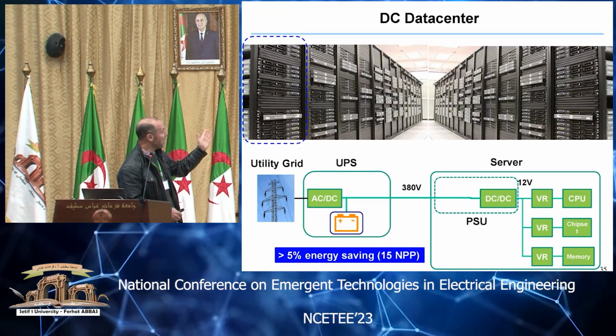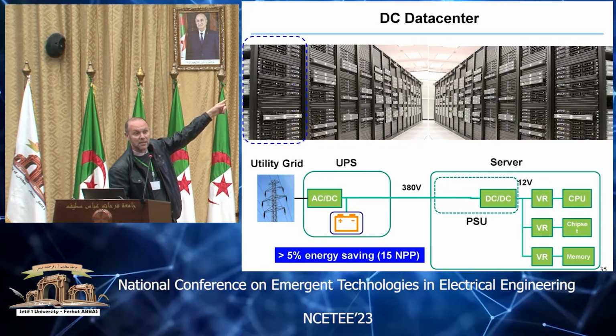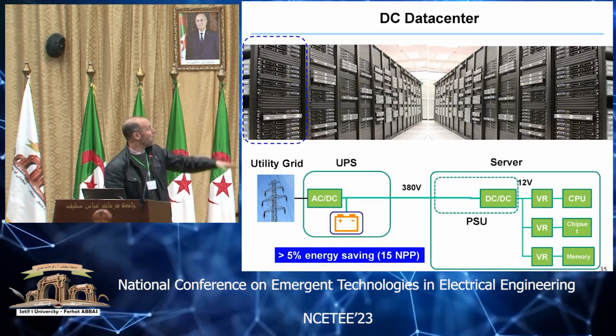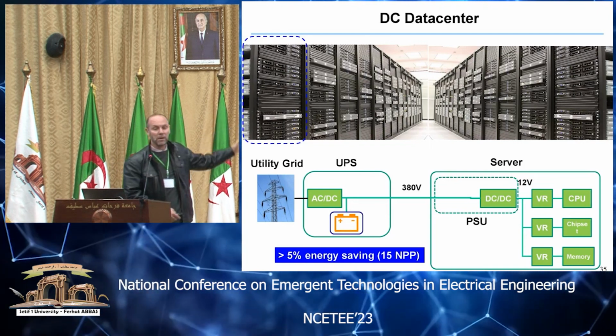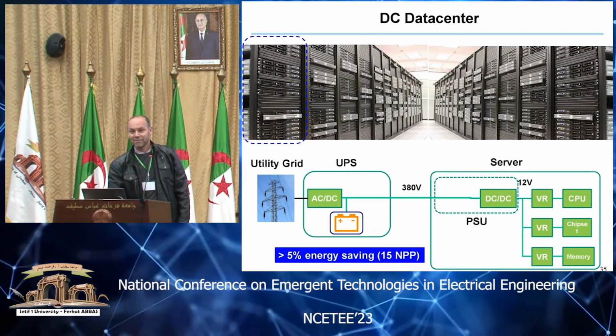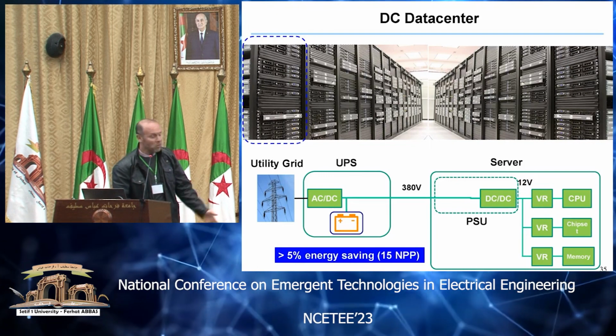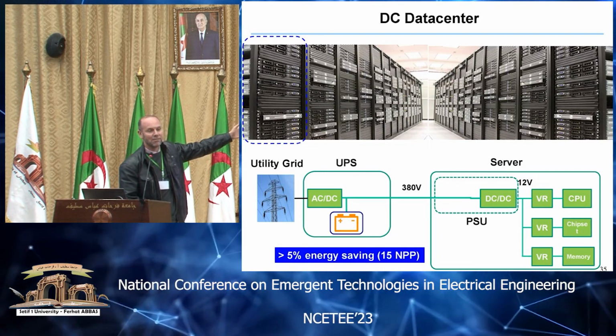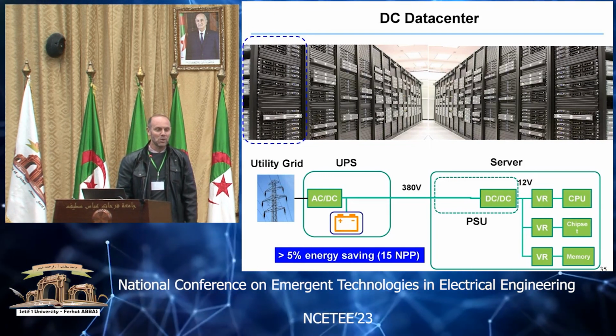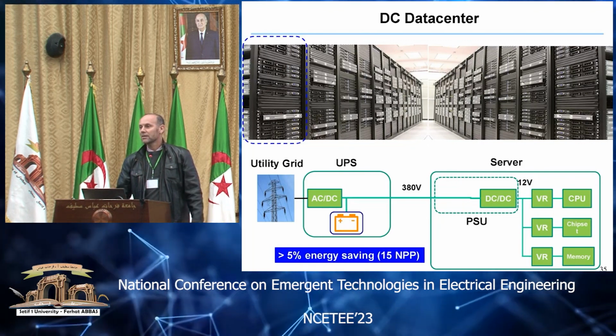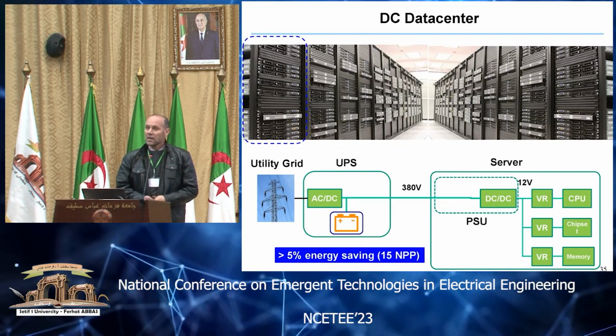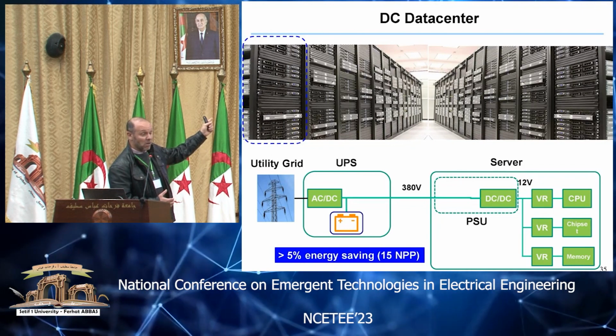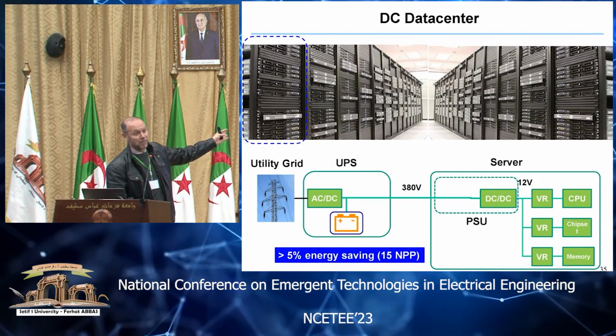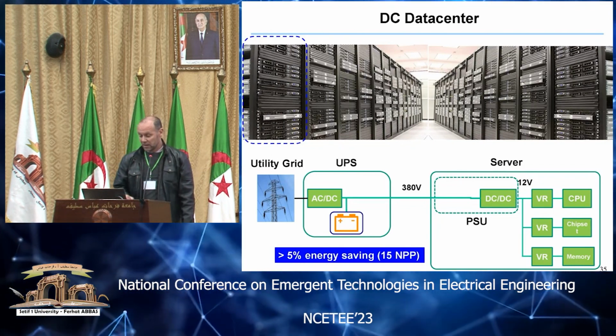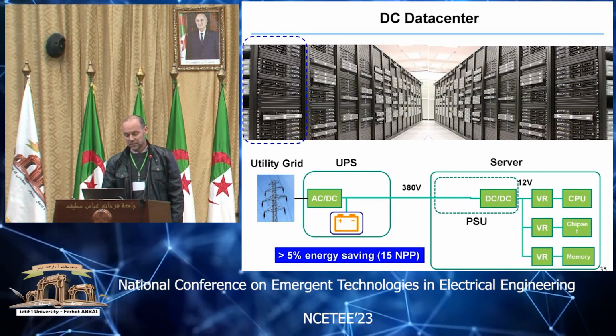So moving from AC to DC data centers can save us a lot. How about if we change this grid with PV? If we change it with PV, we don't need the AC to DC conversion anymore. We can supply directly to the batteries and then to the UPS system. And only about 5%, maybe less, you can see the amount of saving we can achieve.